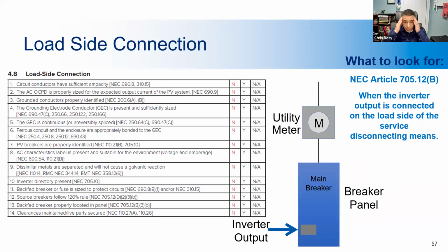All right, so now we're going to talk about the interconnections. First, we'll talk about a load side connection. This is a simple drawing of where the load side connection is made. It's when the inverter output is connected on the load side of the service disconnecting means, which is the main breaker, basically. This is typically accomplished through the use of a backfeed breaker, which you have to locate on the opposite side of the panel as the main breaker. This is so as not to overload the bus bar.